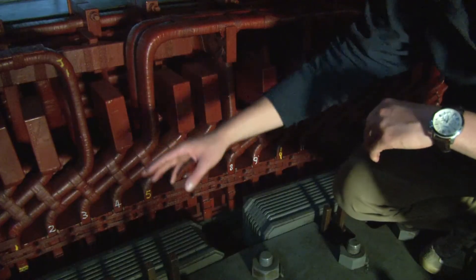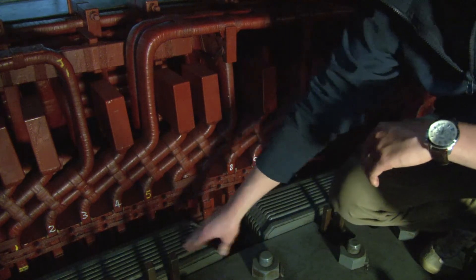We're actually now down in the generator pit. We're privileged to be right on top of the generator - this whole thing would be moving. This moves at about 225 RPM, so very fast. That's a huge amount of energy in these things. So what we do is we power up these coils - we have 48 of these coils. Normally they don't do anything until you power them up, and then they turn into magnets.